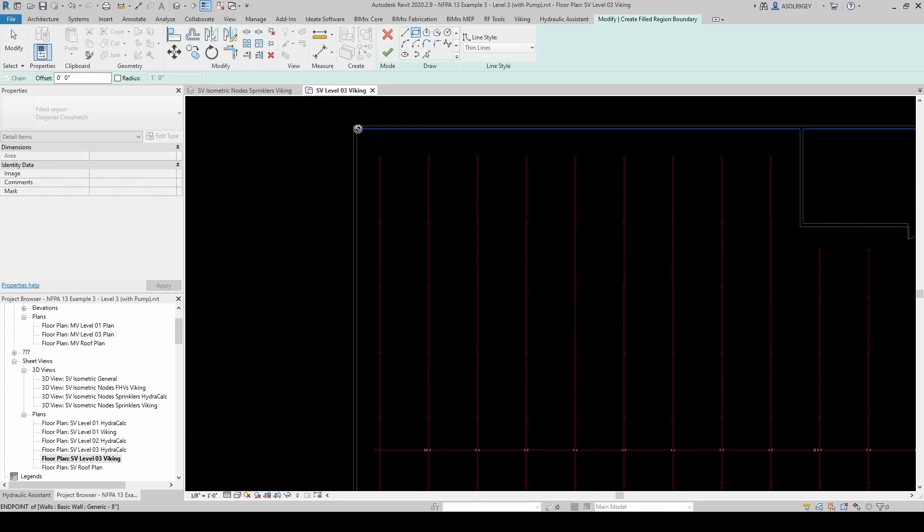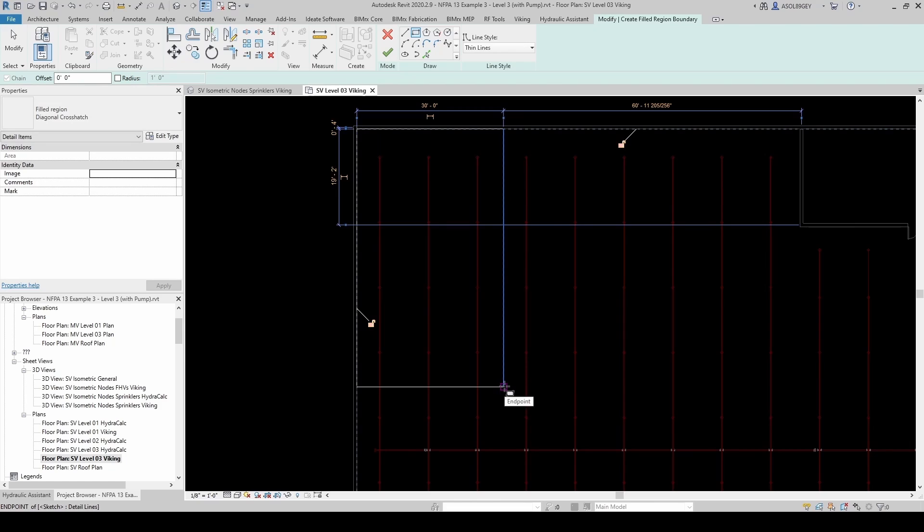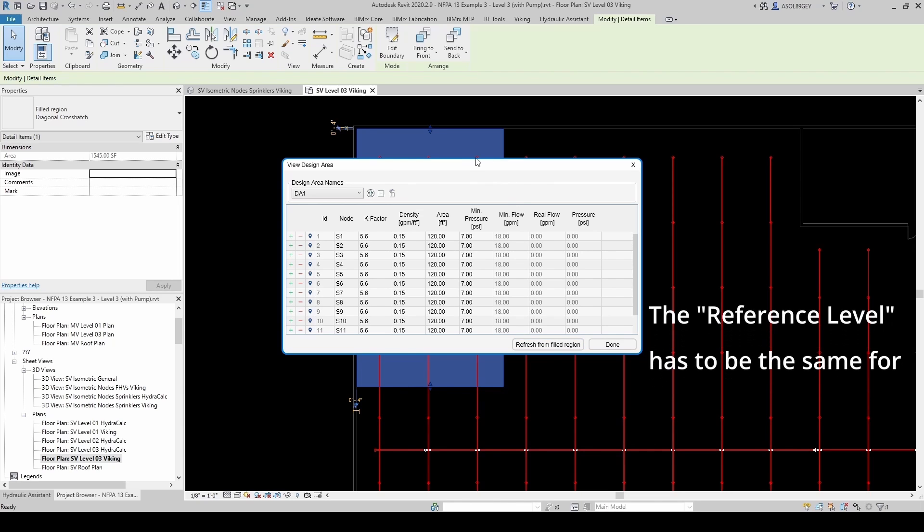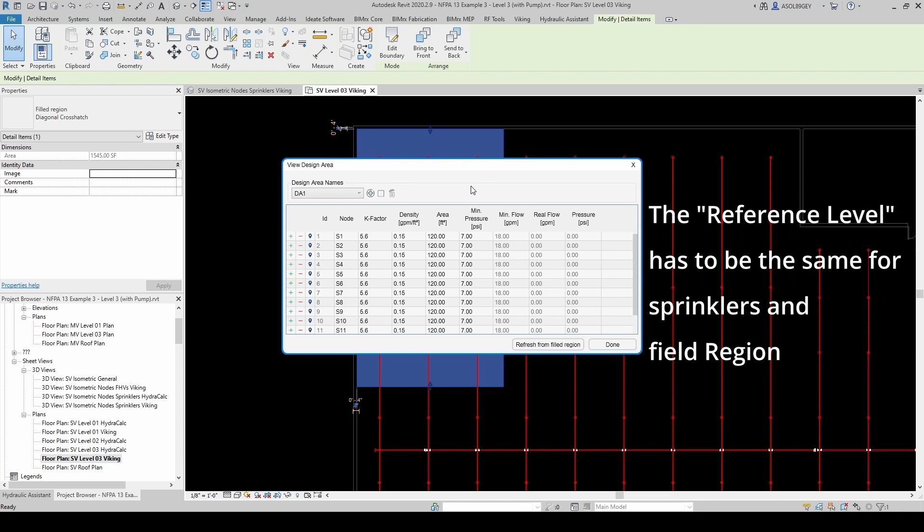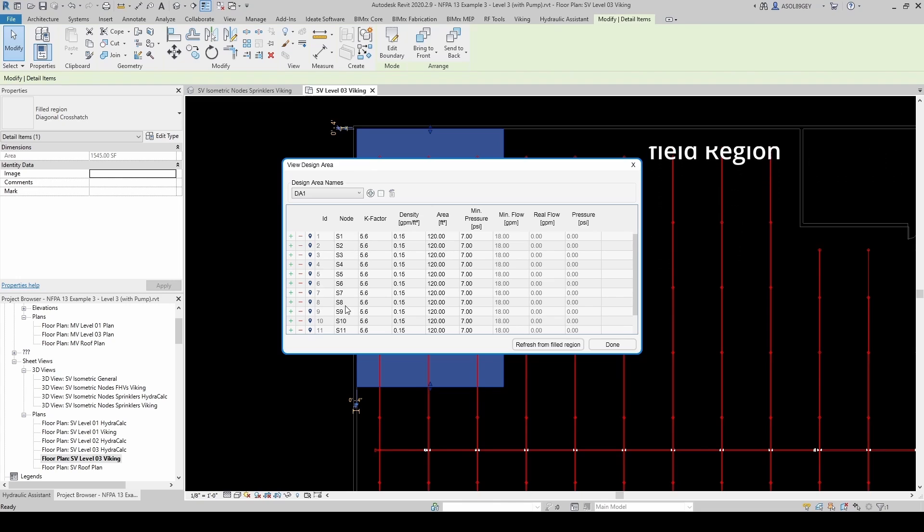And I'm going to click OK. We can see that our area is about 1,500 square feet. So that's good. We're just a little bit above that. And when you do this, make sure that you create the filled region in the same level where the sprinklers are located. If not, it's going to give you an error. So now we can see all our sprinklers. We can see that we grabbed 12 sprinklers, as expected.